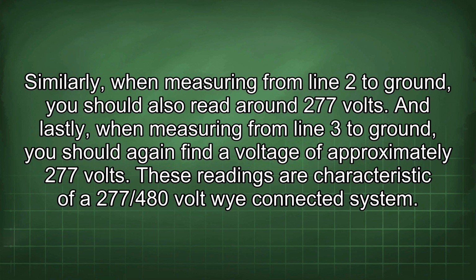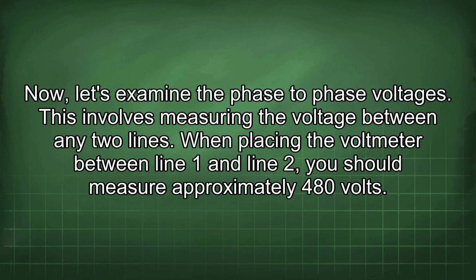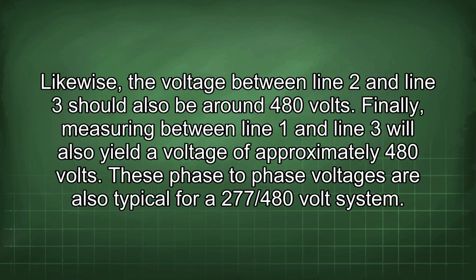These readings are characteristic of a 277/480 volt Y-connected system. Now, let's examine the phase-to-phase voltages. This involves measuring the voltage between any two lines. When placing the voltmeter between line 1 and line 2, you should measure approximately 480 volts. Likewise, the voltage between line 2 and line 3 should also be around 480 volts. Finally, measuring between line 1 and line 3 will also yield a voltage of approximately 480 volts.